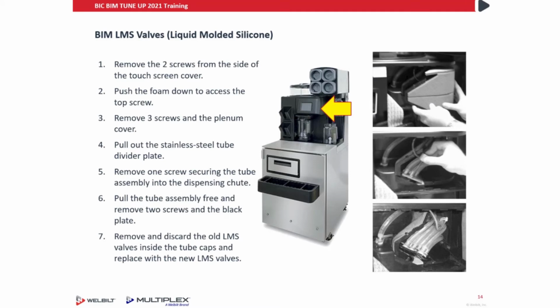On the BIM, remove the 2 screws from the side of the touchscreen cover. Push the foam down to access the top screw. Remove 3 screws and the plenum cover. Pull out the stainless steel tube divider plate. Remove 1 screw, securing the tube assembly into the dispensing chute. You can then pull the whole tube assembly free and remove the 2 screws and the black plate. Remove and discard the old LMS valves inside the tube caps and replace with the new LMS valves.